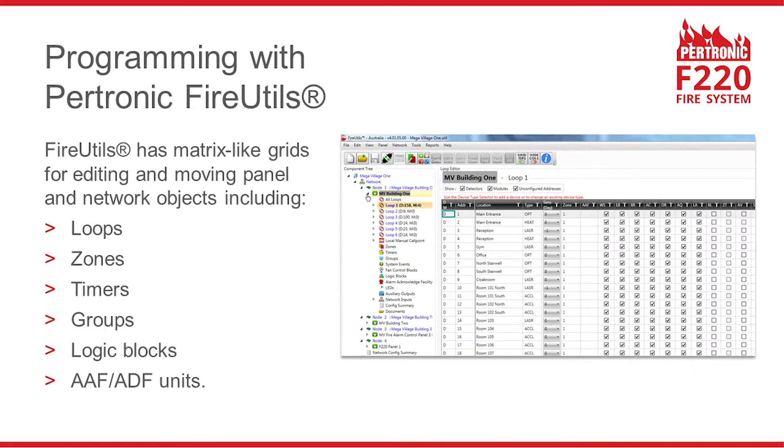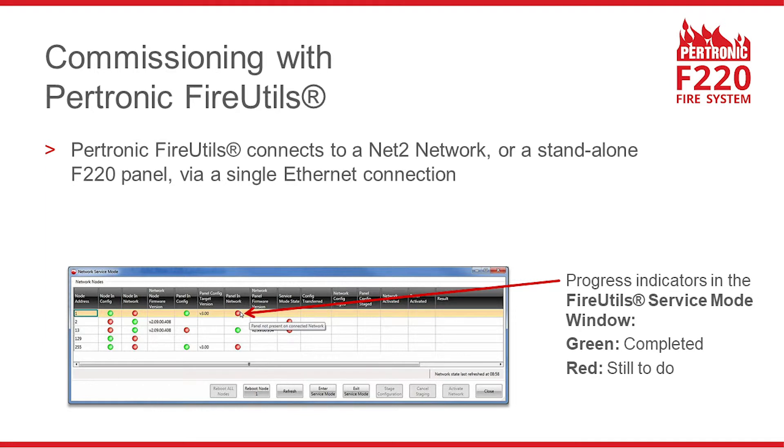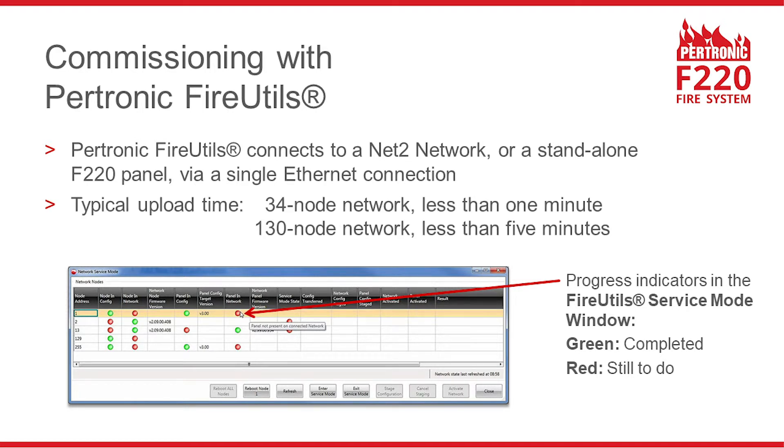Pertronic FireUtils provides matrix-like grids for editing and moving panel and network objects, making it easy to commission or update an F220 system. FireUtils connects to a Net2 network or a standalone F220 panel via a single Ethernet connection. Typically it takes less than a minute to upload a full configuration for a 34-panel network, and the configuration for a network with 130 nodes can be uploaded from a single point in less than 5 minutes.